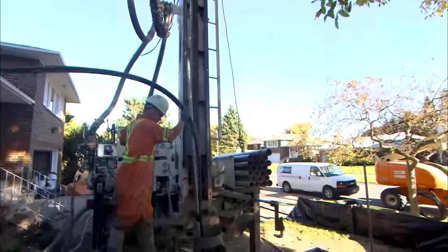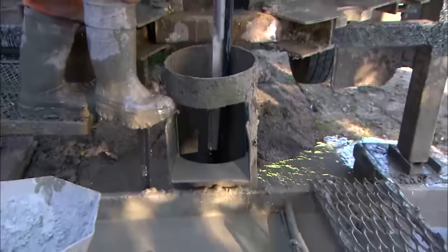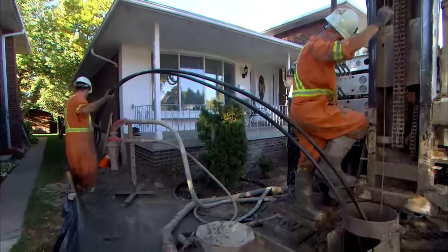As soon as we complete drilling each hole, we have to pull all our rods out one at a time, and then we put our loop down the hole. It's lowered down with a winch cable, drops the loop to the bottom of the hole, and then we pull that back out with the winch, leaving the loop in the ground. Then onto the grouting.